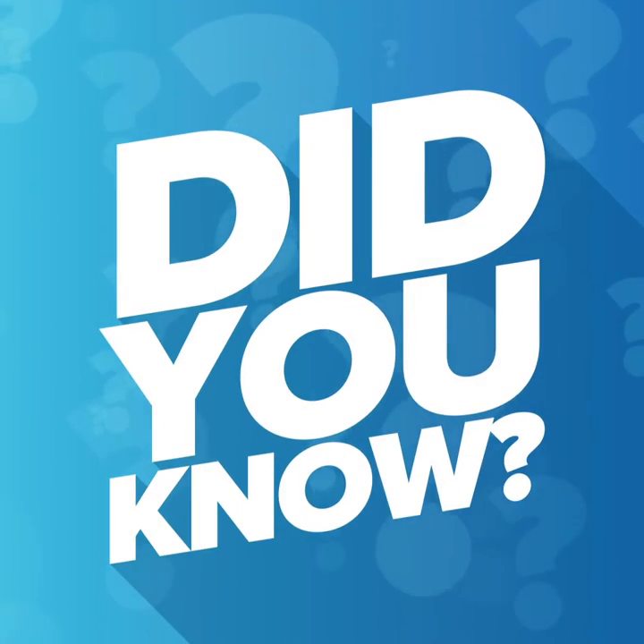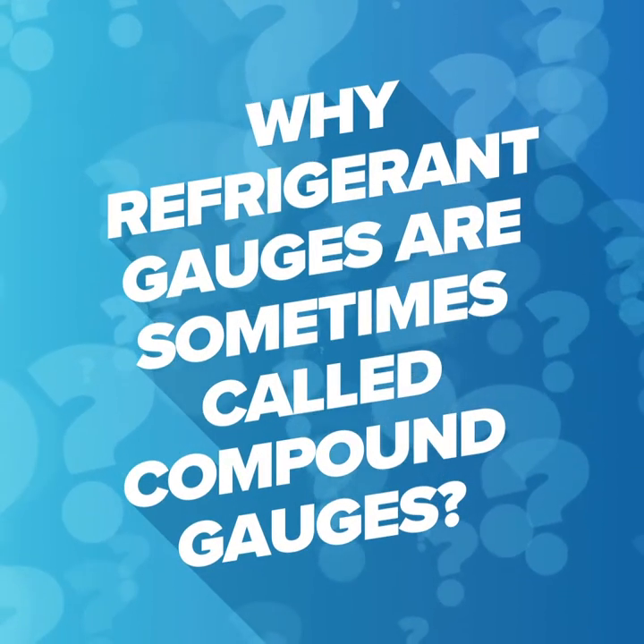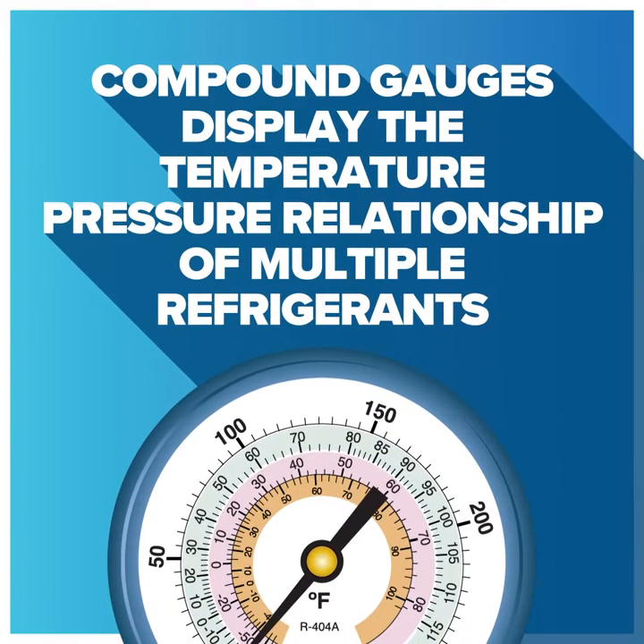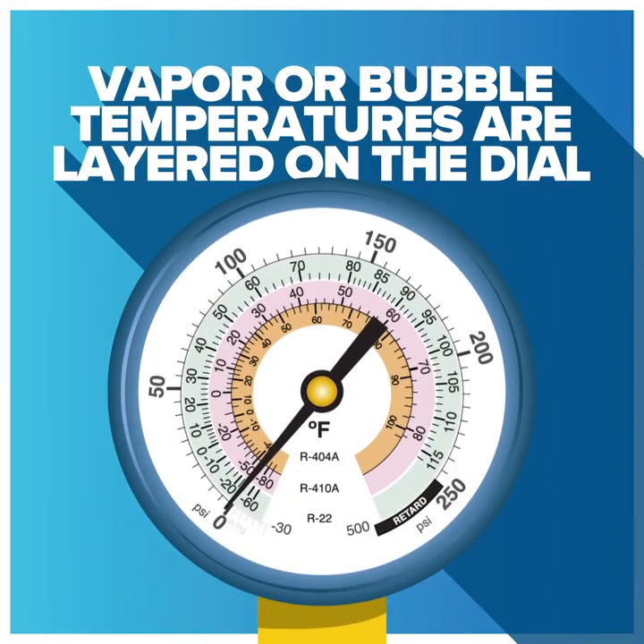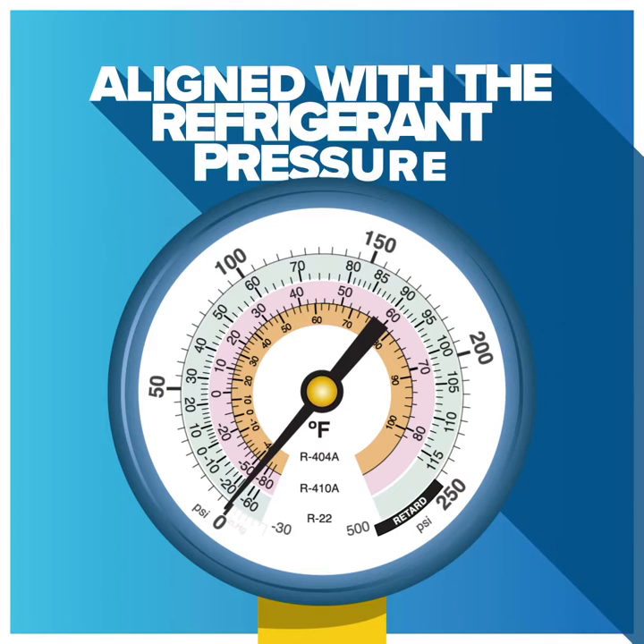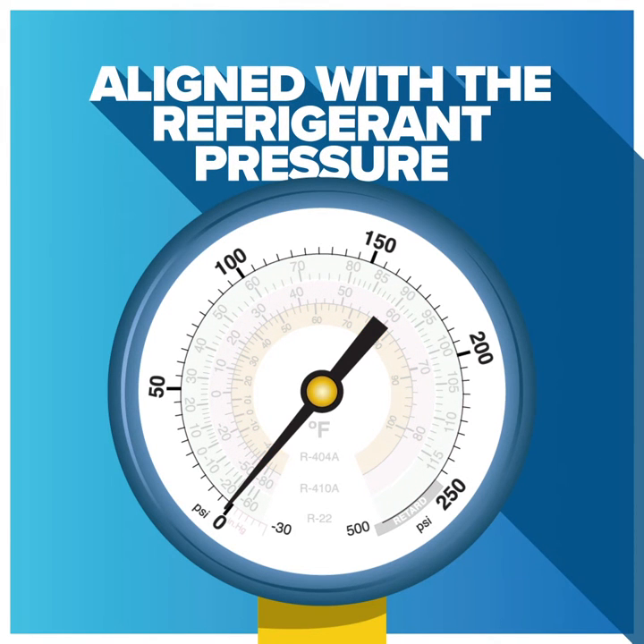Did you know why refrigerant gauges are sometimes called compound gauges? Compound gauges display temperature-pressure relationships of multiple refrigerants. It means that vapor or bubble temperatures are layered on the dial and can be aligned with refrigerant pressures, which are always displayed on the outermost set of graduated numbers of the gauge.